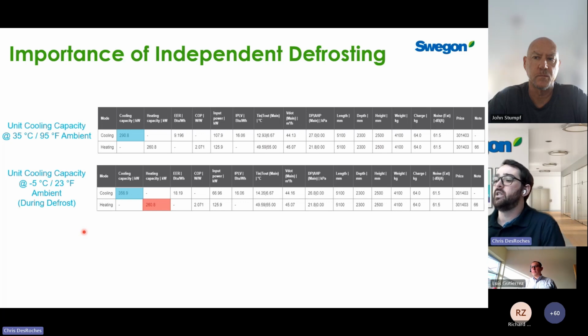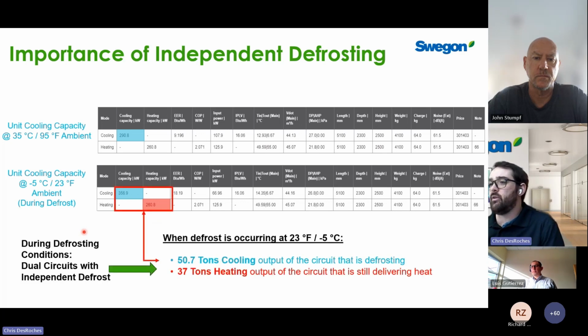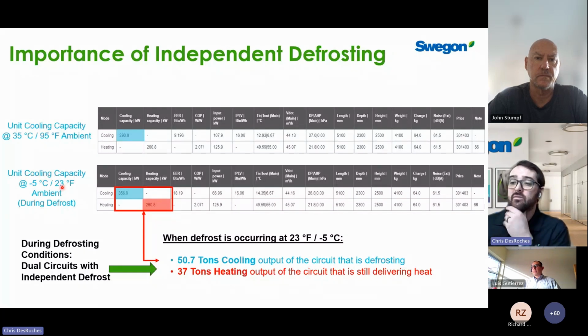of having independent defrosting. If we look at a 100 nominal ton unit rated, we would actually find when we consider the individual outputs of both circuits. So keep in mind one circuit, when we rate this 100 ton unit at 95 F ambient, that's the capacity we have at 95 F. But for any air cooled chiller, because that's really what our unit is in this moment where it's defrosting, it's acting as a chiller. As you decrease ambient temperature outside, our cooling capacity actually goes up. So if you compare the output at 95 F ambient versus 23, which is the moment we're defrosting, you'll find you actually get 20% more cooling capacity. So we often think with a dual circuit heat pump that we're canceling out.